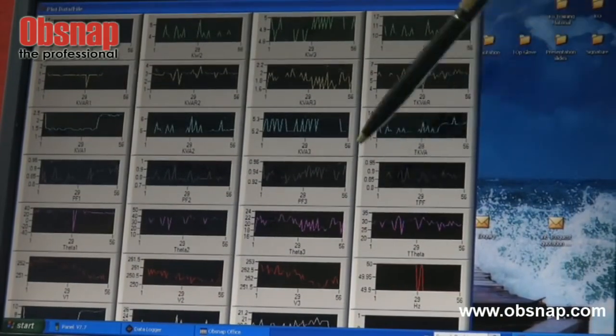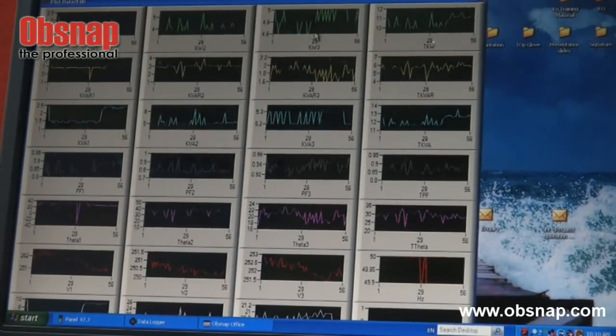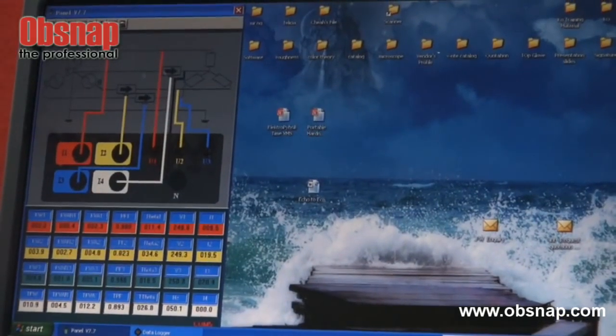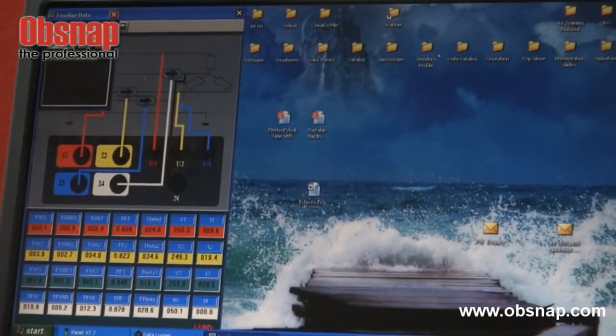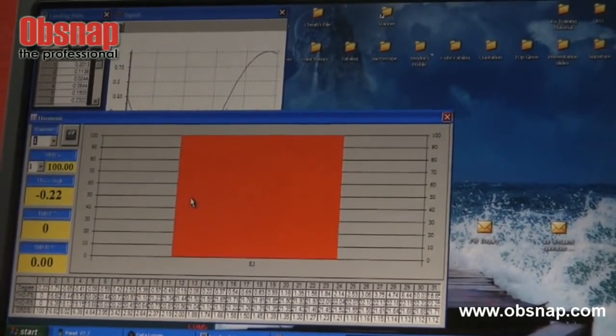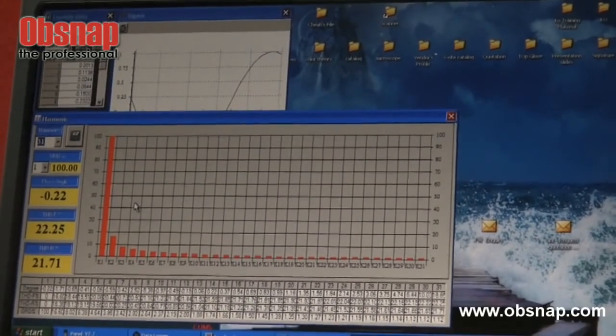The software also shows harmonics — the harmonics level. We can view more information, including harmonics at our fundamental frequency of 50 Hz, shown in graphical display as a harmonic spectrum curve.